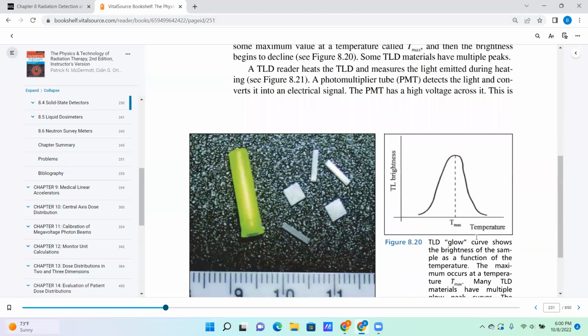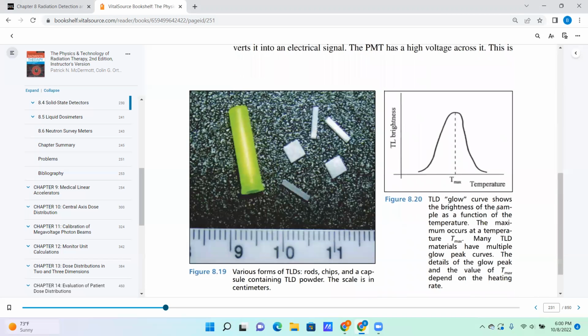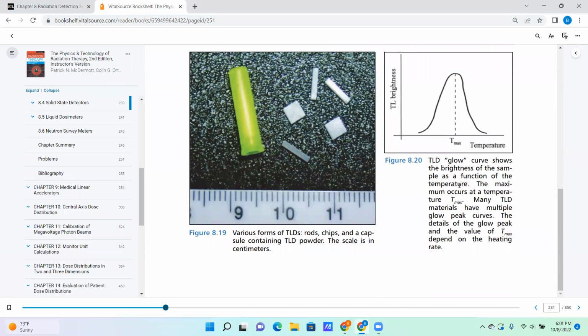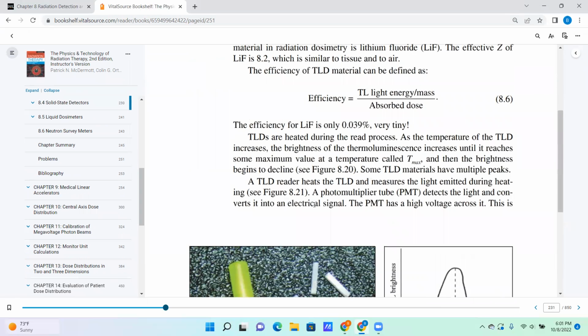So you can see here the TLD glow curve shows the brightness of the sample as a function of temperature. The maximum occurs at a temperature Tmax. Many TLD materials have multiple glow peaks. The details of the glow peak and the value of Tmax depend on the heating rate. So a TLD reader heats the TLD and measures the light emitted. A photomultiplier tube detects the light and converts it into an electrical signal.